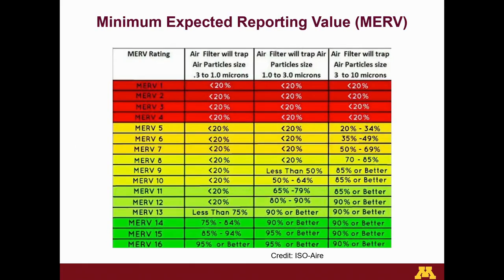Before I go on to the results, I think it's important. In the world of filtering pig barns, we talk in MERV ratings, MERV 14, 15, 16. Focus down here. A MERV 14 filter on the E1 particles, classified as 0.3 to 1 micron, is about 75% fractional efficiency. The MERV 15 is about 85, 90%. MERV 16, 95% is the definition there. And so that's the world we live in. In bioaerosol engineering, they use 1 minus fractional efficiency, which is penetration, because there are filters regardless of type. We work in log reductions. We work in going from some level upstream to some level downstream. So it's important to understand that.